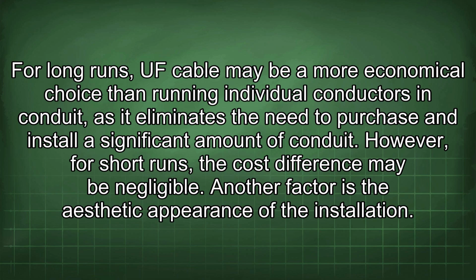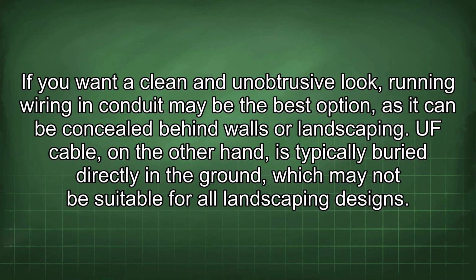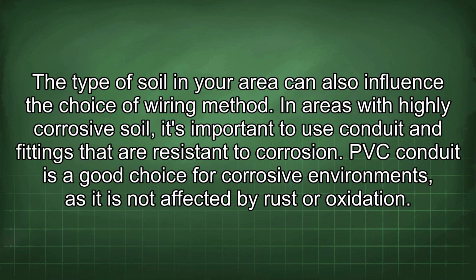Another factor is the aesthetic appearance of the installation. If you want a clean and unobtrusive look, running wiring in conduit may be the best option, as it can be concealed behind walls or landscaping. UF cable, on the other hand, is typically buried directly in the ground, which may not be suitable for all landscaping designs. The type of soil in your area can also influence the choice of wiring method.